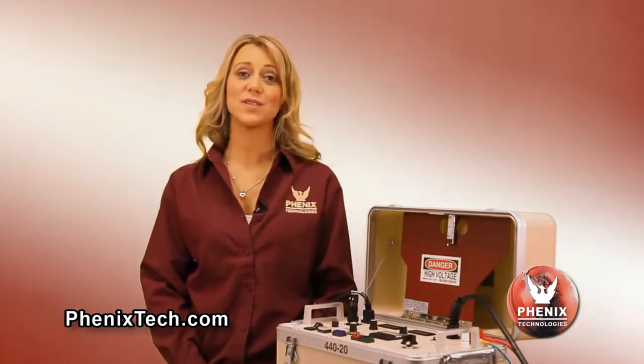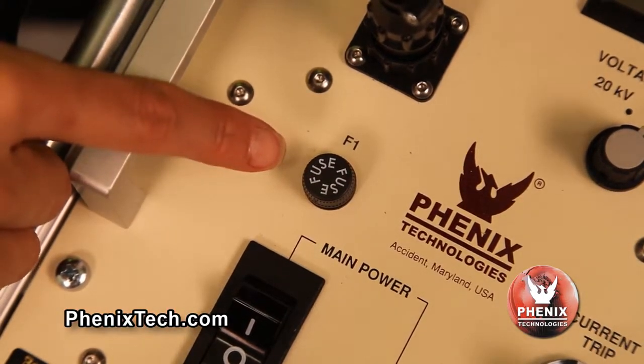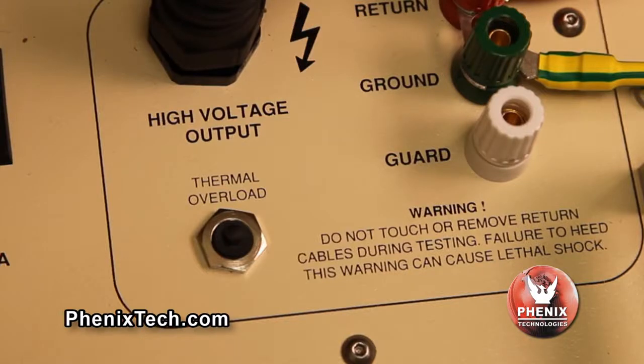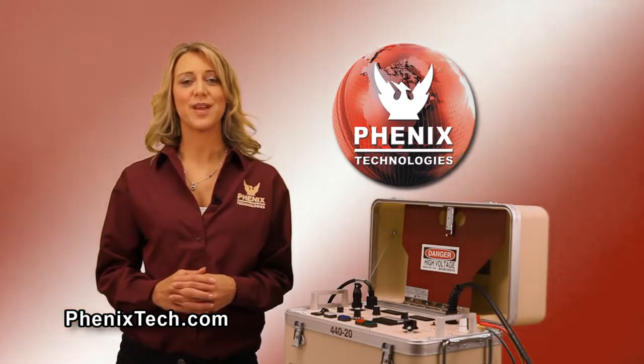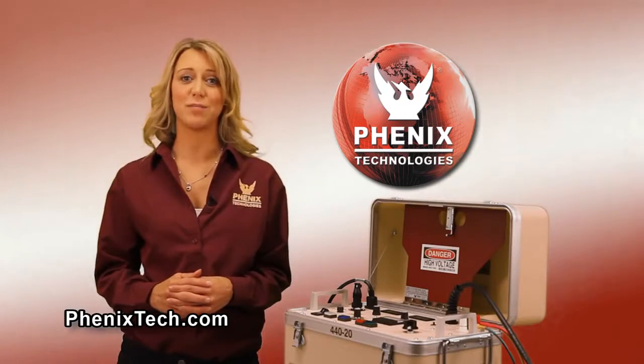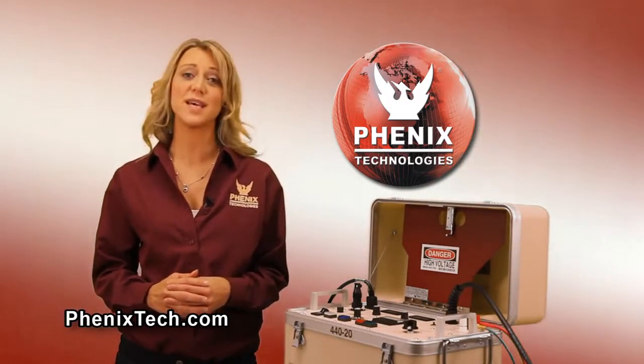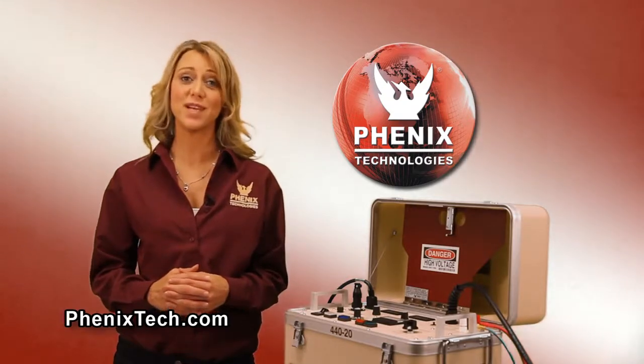Our hi-pots have a built-in discharge circuit. This feature allows any residual charge that may remain on the test object to discharge after the hi-pot is turned off. The fuse is sized to protect the control power circuit. The thermal overload protects the high voltage transformer. Thank you for watching this video. Please go to our website for additional information regarding our portable DC hi-pots and the many other high voltage and high current test sets manufactured by Phenix Technologies.